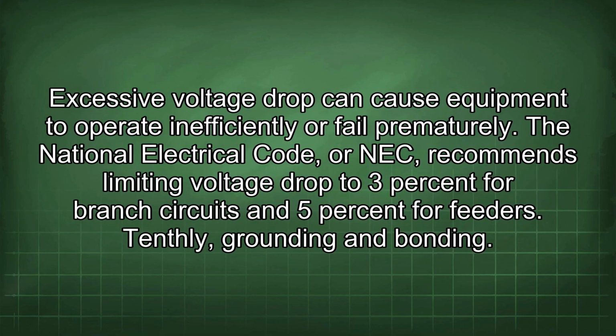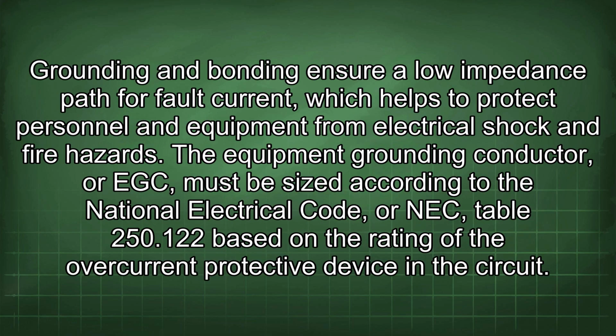Excessive voltage drop can cause equipment to operate inefficiently or fail prematurely. The National Electrical Code, or NEC, recommends limiting voltage drop to 3% for branch circuits and 5% for feeders. Tenthly, grounding and bonding. Grounding and bonding ensure a low impedance path for fault current, which helps to protect personnel and equipment from electrical shock and fire hazards.